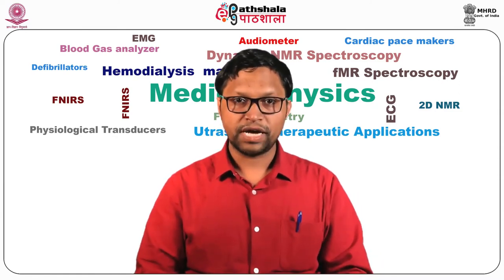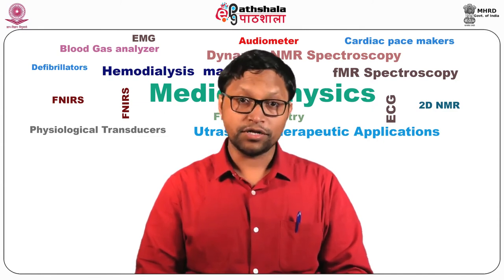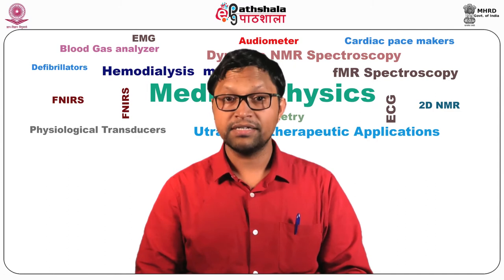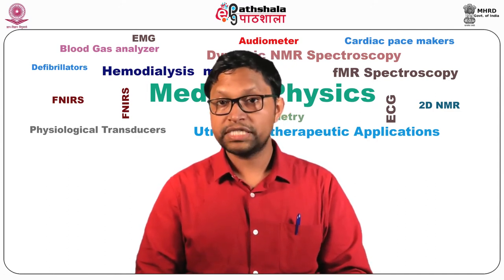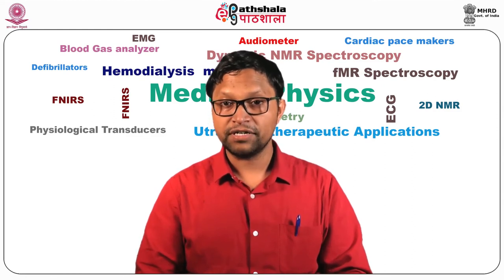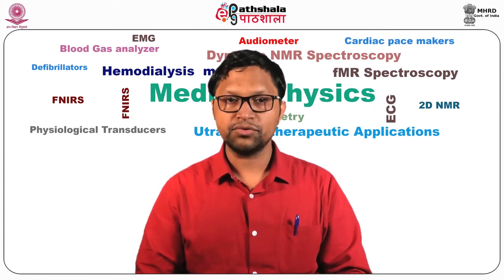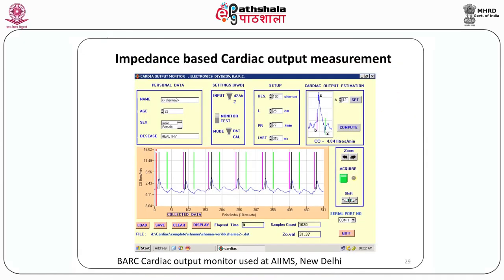The electrodes for thoracic impedance cardiography may be of various types and can be placed vertically, horizontally, or one can use spot electrodes in different configurations. This slide shows typical vertical placement of silver braided wire electrodes. For the sake of convenience, many researchers use ECG-type spot electrodes. This shows a typical graphic user interface of an impedance cardiac plethysmograph developed by BARC in India.